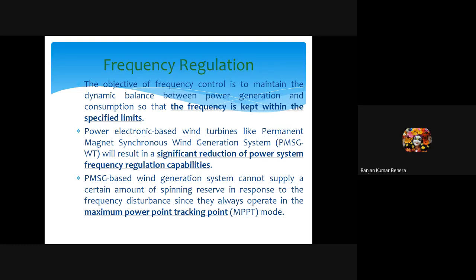When you use power electronics and generators, the generator doesn't have, for example, in your classical generation system you have AGC, automatic generation control, which controls that. And second, you have a flywheel as a storage element where you feed power during the peak hour. So this is also a significant reduction of power system frequency regulation capability.